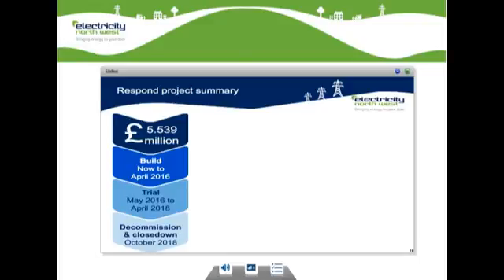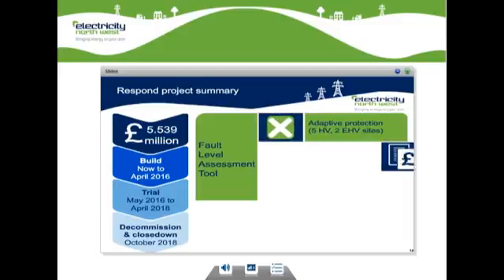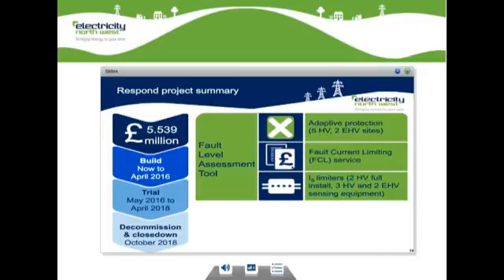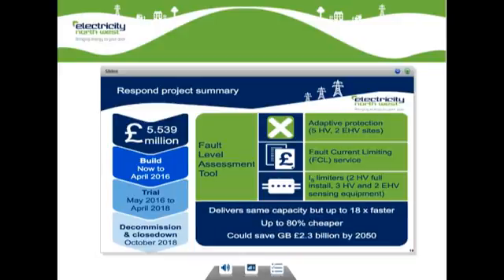So, a quick summary of the Respond project. It's a £5.5 million project which started in January and will run until October 2018. We plan to install the fault level assessment tool and deliver these innovative techniques at the number of sites shown on the slide. The Respond method is expected to release the same capacity as traditional reinforcement, but up to 18 times faster and at a much lower cost, potentially up to 80% cheaper, saving Great Britain up to £2.3 billion by 2050.